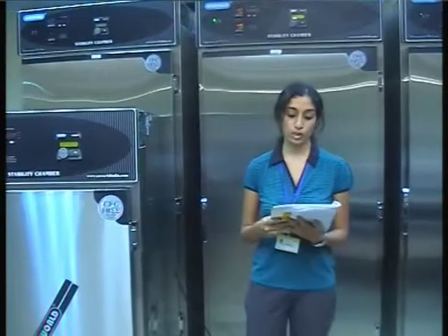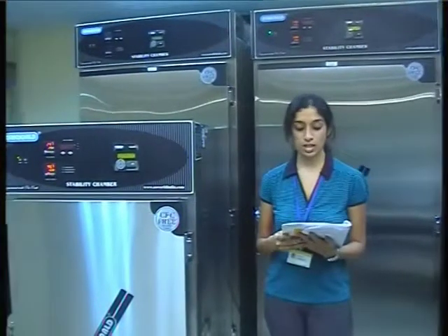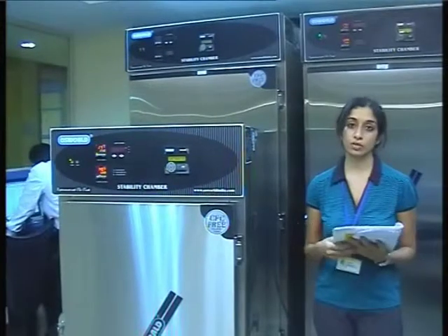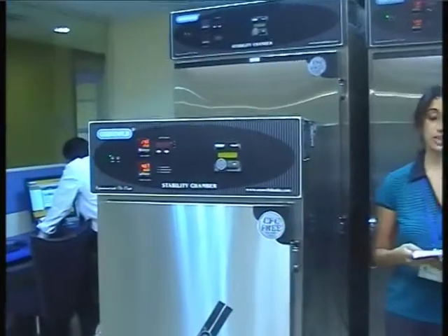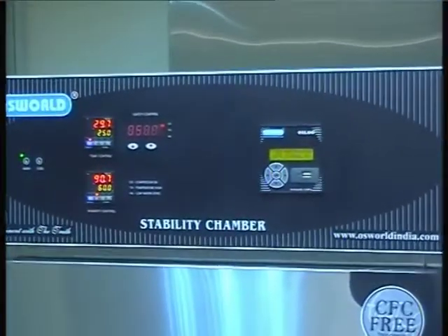In addition, the control panel is also fitted with an exhaust fan. A cooler environment around the equipment improves compressor efficiency by keeping the compressor shell temperature low, which in turn prevents compressor breakdown. The condenser motor, which is mounted near the compressor, is also affected by high ambient conditions, leading to constant motor burnouts. Thirdly, a stabilized input power supply of 230 volts AC.